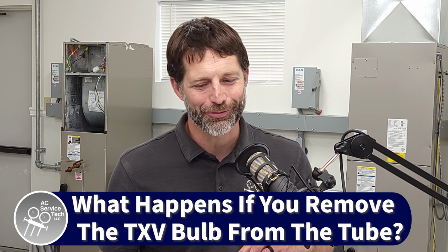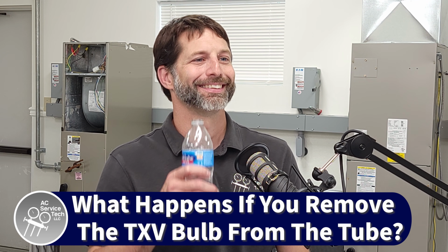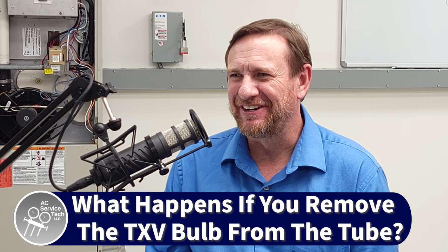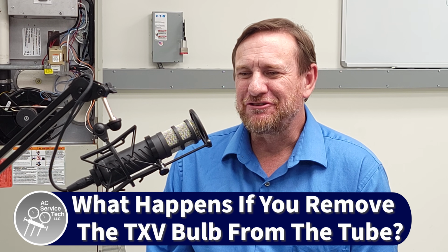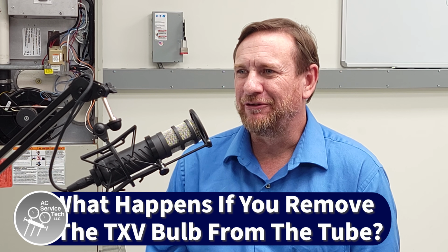And so, yeah. Absolutely. A technician by the name of Carl asks, what happens if you permanently take off the sensing bulb from the TXV or from the line? Kill compressor. That's the short answer of that. So by doing that, they're really fooling the TXV. And the TXV is trying to monitor not only that suction line temperature, but also the suction pressure. And it's trying to control the amount of superheated vapor.